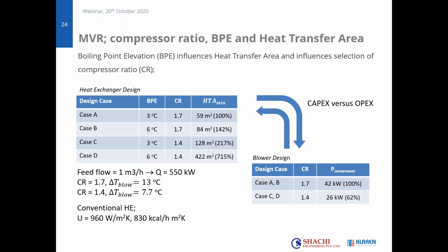So in fact, what you see is that you need in the design to make a decision between investing in heat transfer area, maybe then lowering the compressor ratio that you need to run at, or going to, let's say, a lower investment, but that means more operational cost because you need to run with a higher compressor ratio. So this is really an evaluation that you need to make between those two elements.